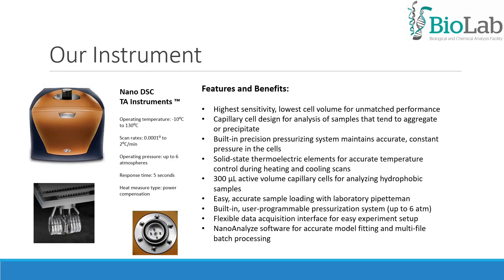Our instrument is the NanoDSC from TA Instruments. It has an operating temperature from minus 10 degrees Celsius to 130 degrees Celsius, scan rates from 0.0001 to 2 degrees per minute, operating pressure up to 6 atmospheres, response time of 5 seconds, and the heat measurement type is by power compensation. This device has a capillary cell design for analysis of samples that tend to aggregate or precipitate. Cell volume is 300 µL. The NanoAnalyze software allows for accurate model fitting and multi-file batch processing.